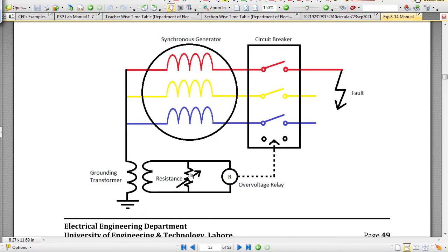Then a resistance or reactance will be inserted on the secondary side of this distribution transformer or grounding transformer, and this method is used to limit the fault current. And as the fault current will become very small due to insertion of this high impedance in the neutral circuit, it is very difficult to detect the ground fault by monitoring the fault current in these three phases, phase A, B, C.